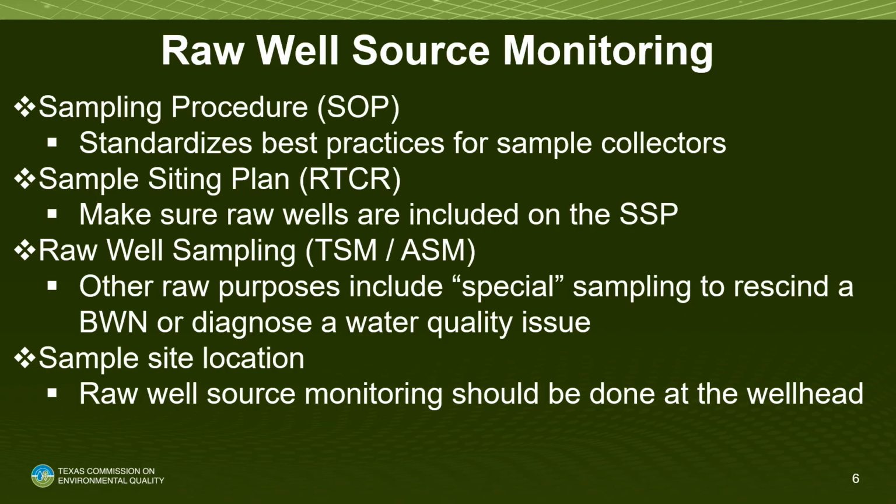And then the raw well source monitoring, I just wanted to mention it should be done at the wellhead. There should be a sample tap on your wellhead. I have seen though several times, through the years, that sometimes wells don't have a sample tap on them. So the groundwater rule requires it to be sampled at the wellhead, and we also have a subchapter D rule that requires a sample tap at the well. So in the situations that I've seen it, it's always led to the system getting a plumber to come out and install that sample tap on the wellhead.